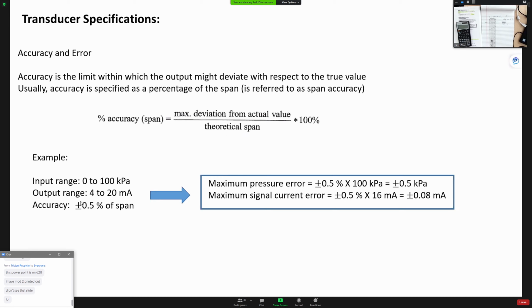So if you have an accuracy of 0.5%, your input is from 0 to 100 kilopascal, and you could have 0.5% of that 100. So 0.5% of 100 gives you 0.5 kPa, and your reading could be add that or subtract that.